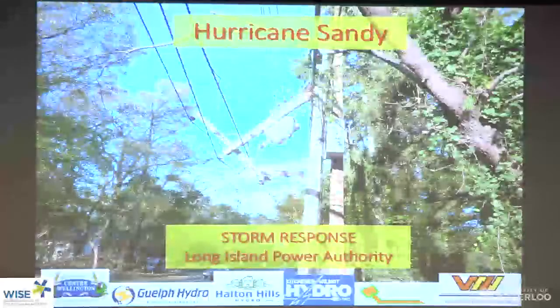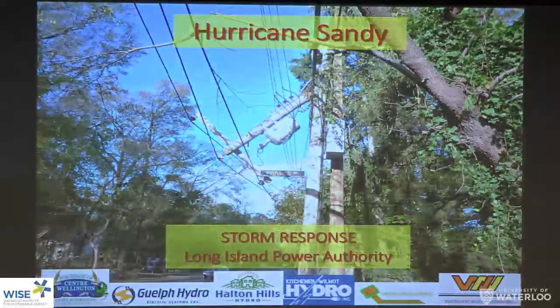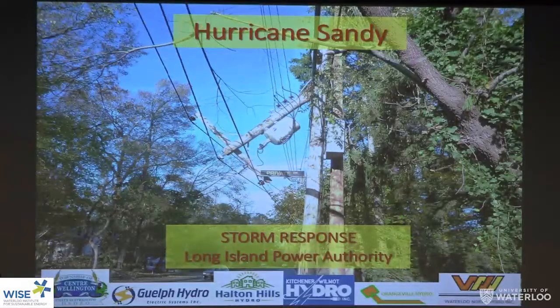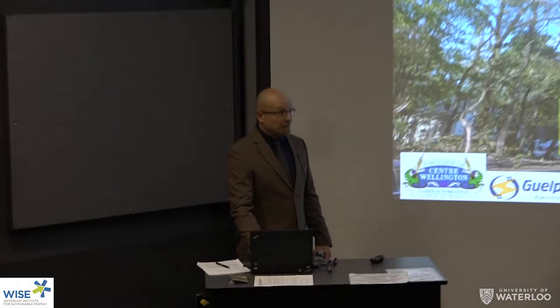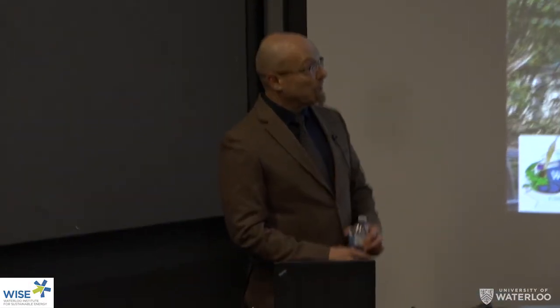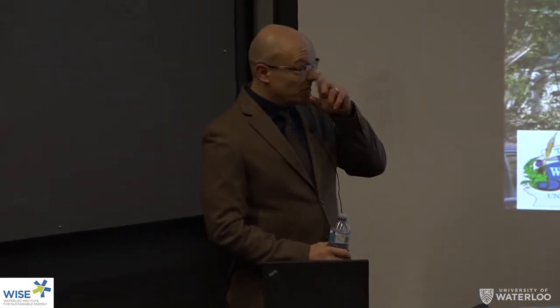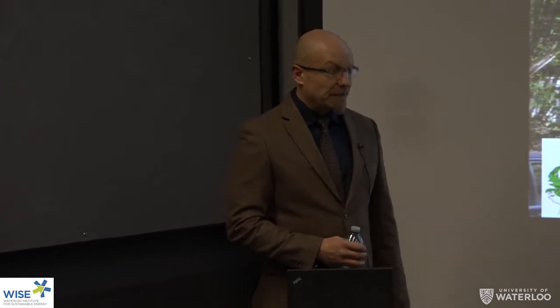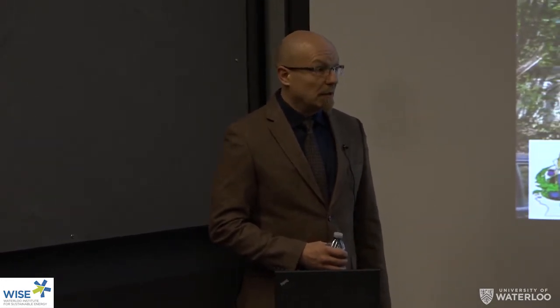Since you have so much trouble with the poles, is there a move towards undergrounding? Yes, there's a lot of areas where every new subdivision is all underground now. That's the new standard. For a lot of the main feeder lines out on the main roads, it's still very expensive - probably 3 to 6 times the cost of overhead to go underground.